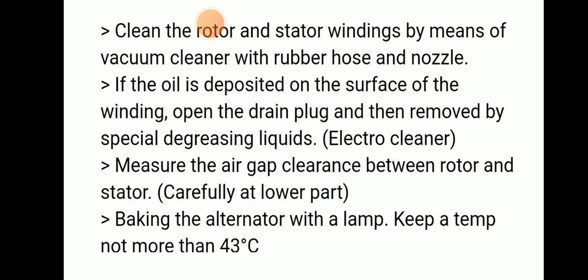Then after this we can measure the air gap between the rotor and stator carefully at the lower part. Like I mentioned, it should be between 1.5 and 2 mm. We can check whether it is up to the level or not. We can check the air gap clearance. Mainly you should check it carefully because at the lower part we have to be very careful.